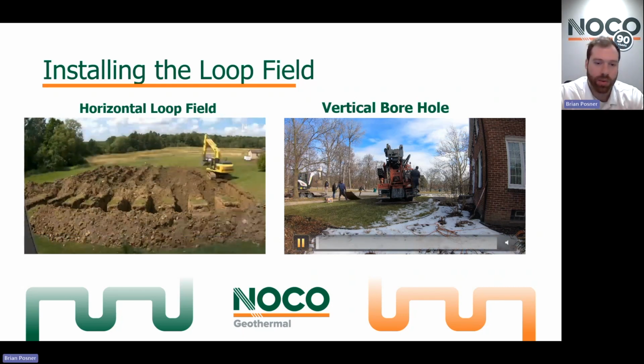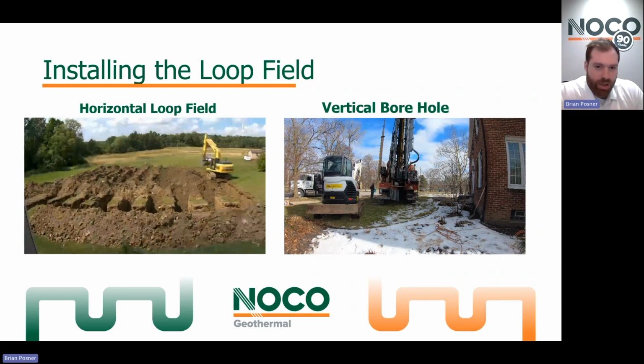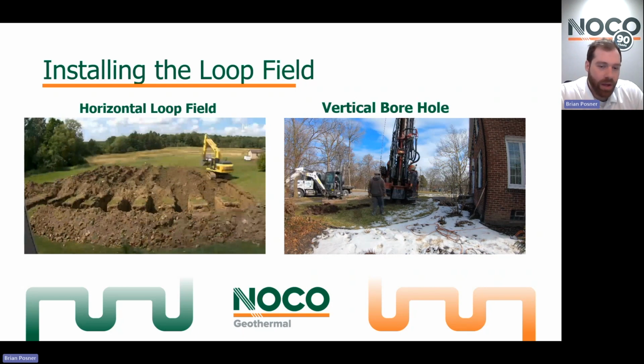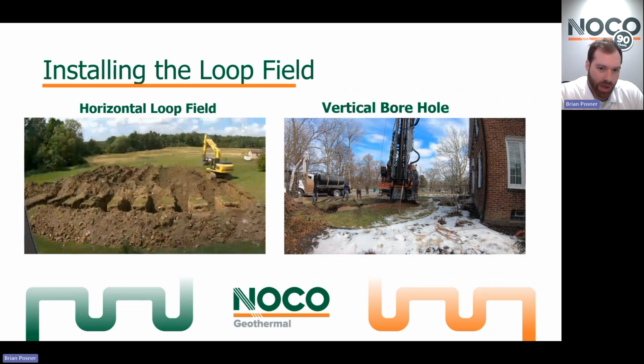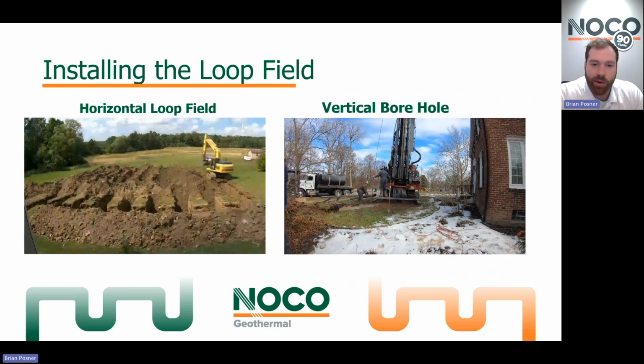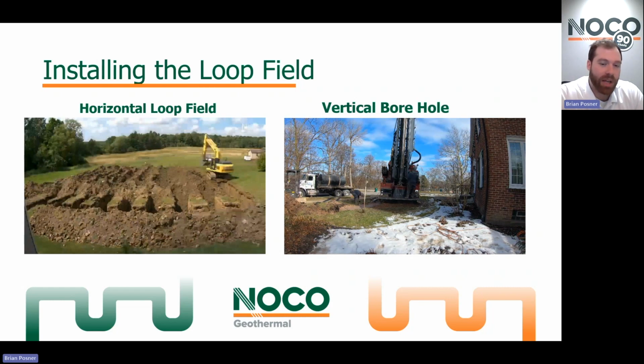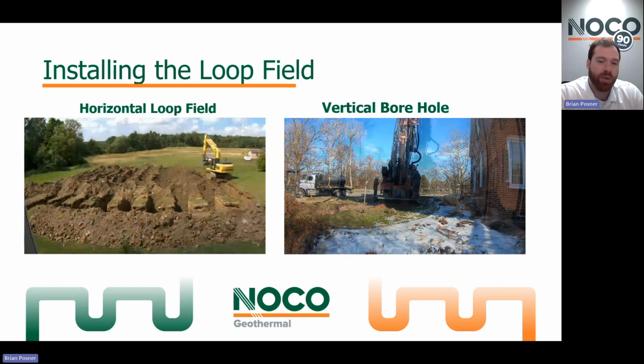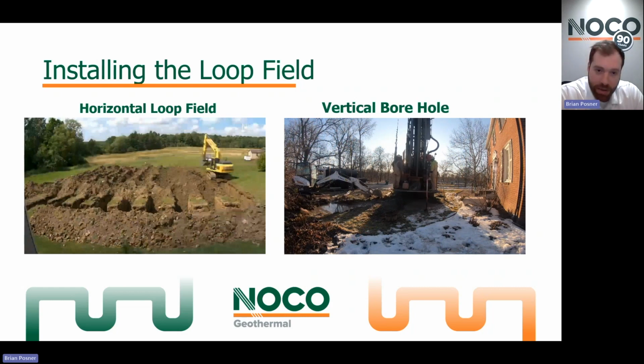Now, a vertical borehole. We have the water well drilling truck come in, and a small excavator to dig what's called a settling pit. The settling pit is for once we hit bedrock, you're going to see a silver liquid coming up out of the hole. That silver liquid is water that we're pumping into the hole to help it cut through the bedrock, and the pulverized bedrock itself that we're pulling up. So again, that silver liquid is nothing more than purely water and pulverized bedrock.